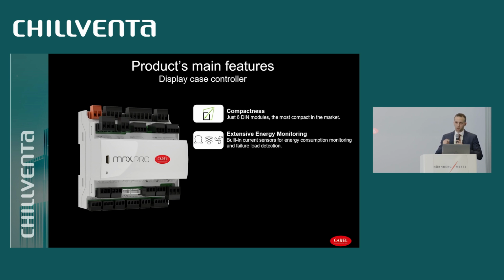Try to imagine that right now, if, for example, the evaporator fans fail, we have to wait for the temperature to rise over the threshold, the high temperature alarm is generated, and so on. With this specific solution, we can say directly that in the store here in Nuremberg, the cabinet 9199, for example, has the digital output number 2 broken, because the controller does not see any current passing by.